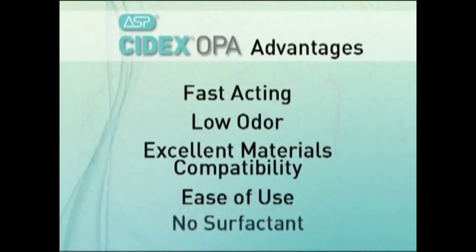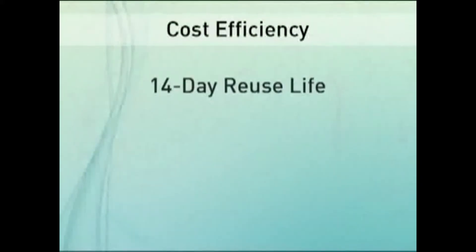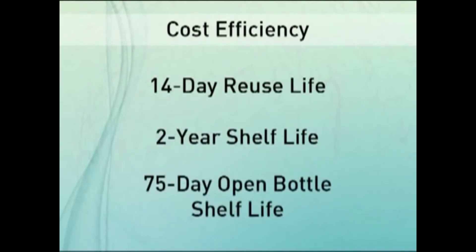The solution contains no surfactants. Another advantage of Cidex OPA solution is cost efficiency, with a reuse life of up to 14 days and a 2-year shelf life. An open bottle containing unused Cidex OPA solution can be stored for up to 75 days.